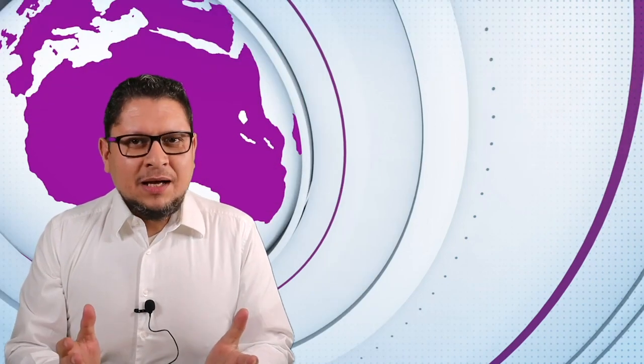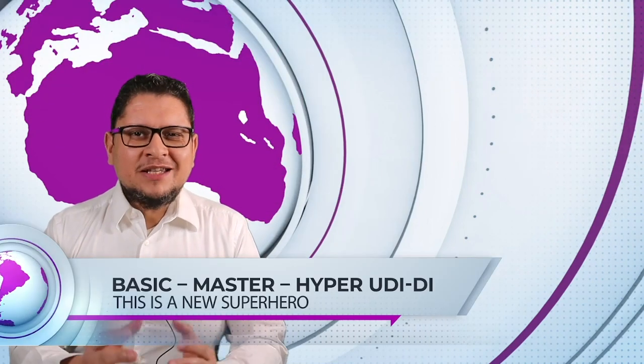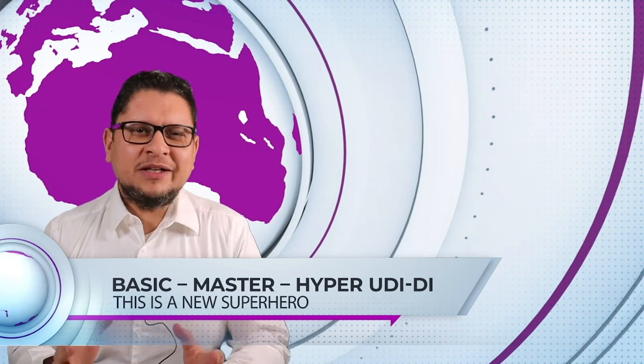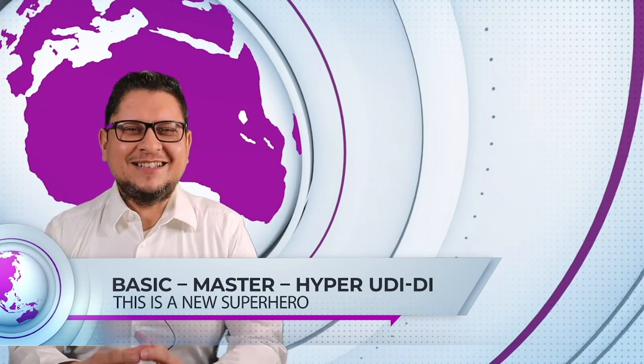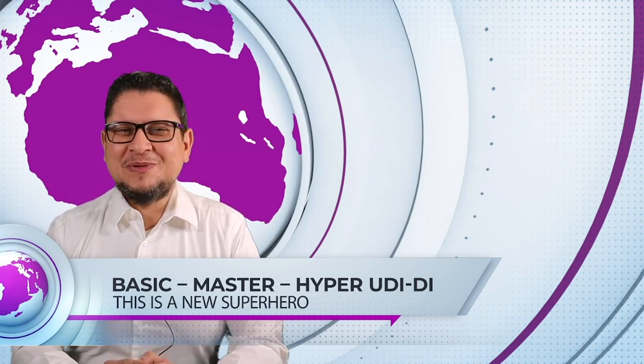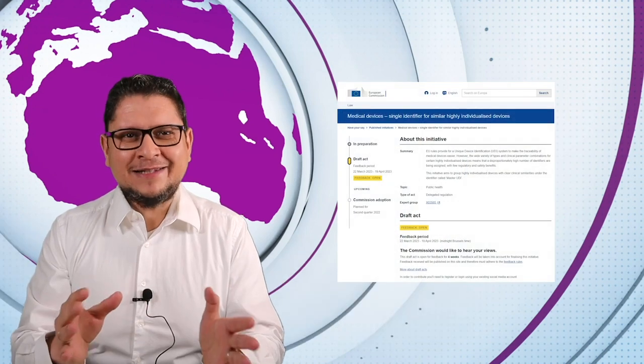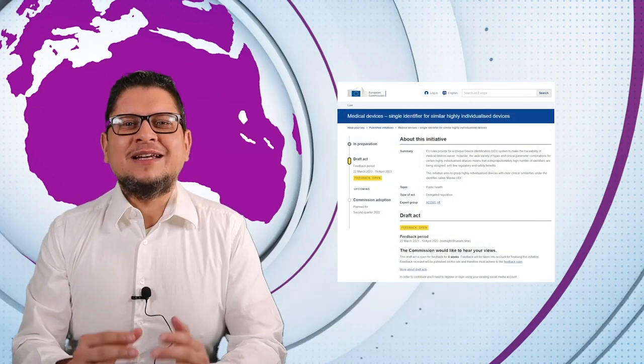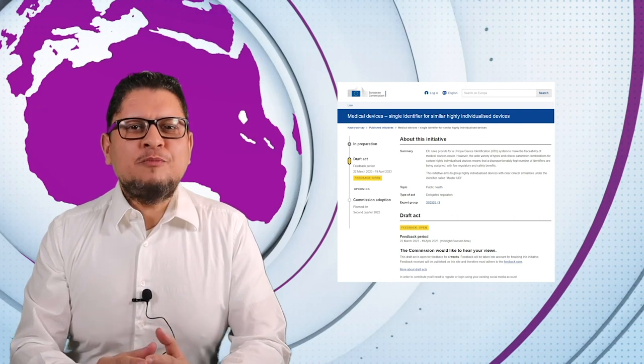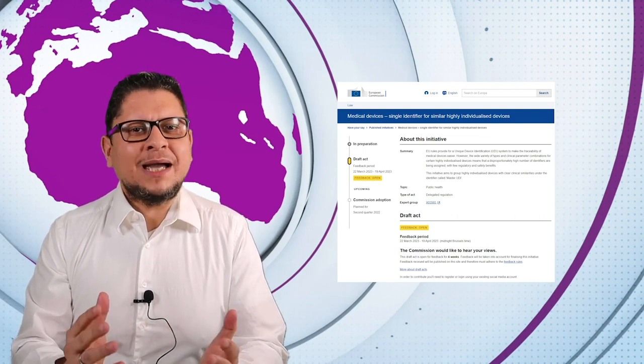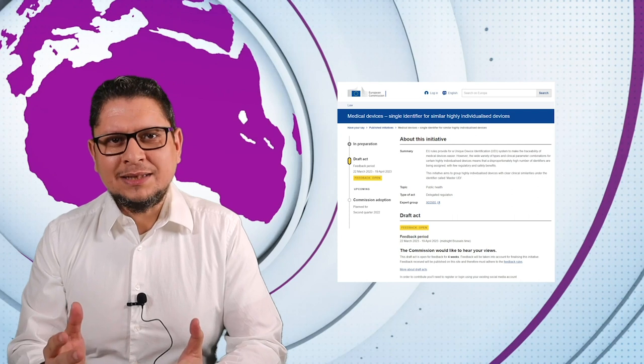After UDI, after basic UDI-DI, we now have a new superhero, Master UDI-DI. I'm sure all other countries will be jealous of us, or will hate us, as they will also have to apply that. The European Union has come up with a new system for identifying contact lenses called the Master UDI-DI.